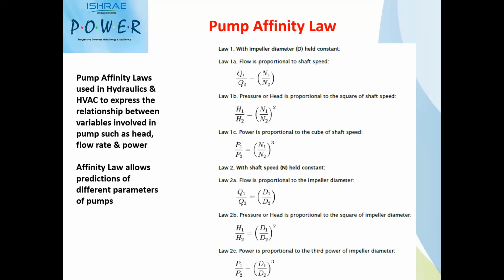Any selection software for that matter, all the pump manufacturers have, is built on these basic formulas, which are called the pump affinity law. So you can have a detailed look at these affinity laws and try to calculate your various flows, heads, and powers based on either your RPM or your impeller size, and try to verify with any particular pump selection of any manufacturer. So this is the basic formula based on which all the selection software is built.